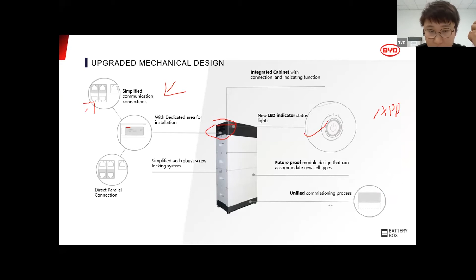And further down, this just summarizes what exactly we're putting there. One thing I want to point out is the system performance in cold temperatures. In the old system, because of software and hardware limitations, if the system reached 12 degrees positive or lower, there would be a current derate on the battery performance. Basically, lithium batteries are just like lead batteries. They don't like cold temperatures. If you run the battery at a low temperature with the same performance, you won't have the battery running for 10 years. It will basically cut the battery life in half.